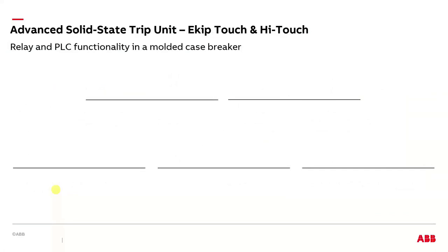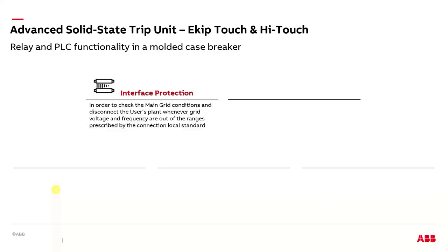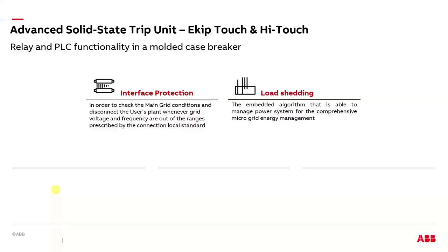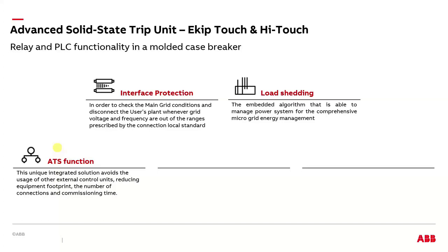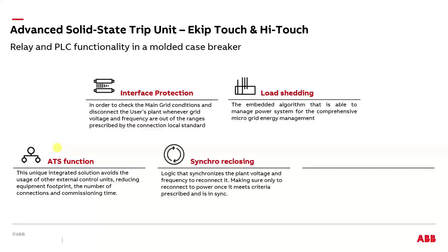And also, we have basically a PLC capability now built into these breakers. We call it interface protection, but we can do logical load shedding based on grid conditions. We can do load shedding based on pure load. There's a built-in transfer switch function, which, if you have two breakers, you can set them up essentially with a single cable, and they'll interlock with each other and operate as a transfer switch. Not a true transfer switch because it's not listed as one, so it would be considered more of an automatic throwover, but it'll do all the functions that a transfer switch will do, with just two breakers and no PLCs. Synchro reclosing, so we can do paralleling boards with molded case circuit breakers.